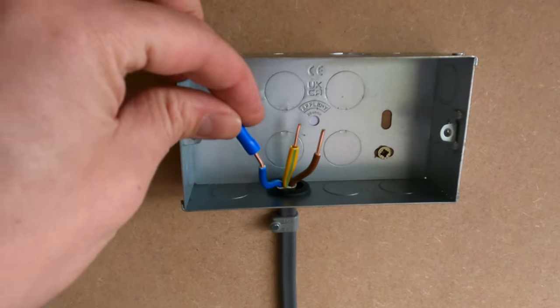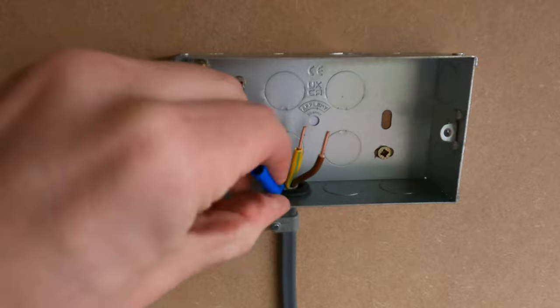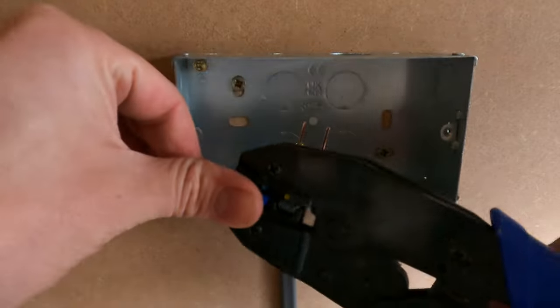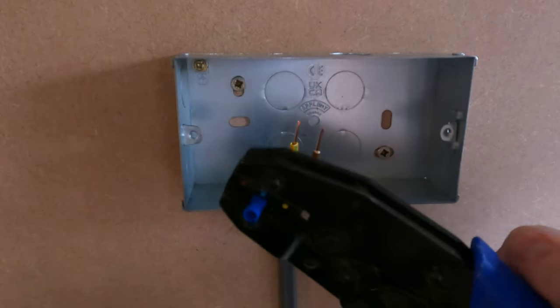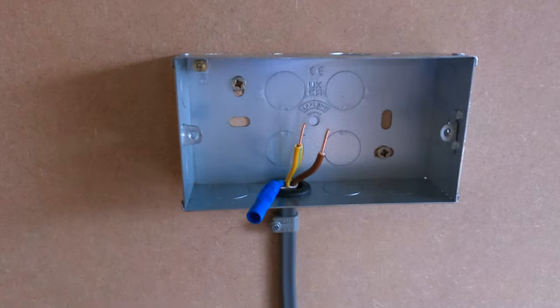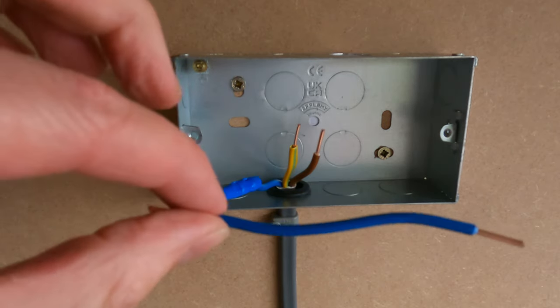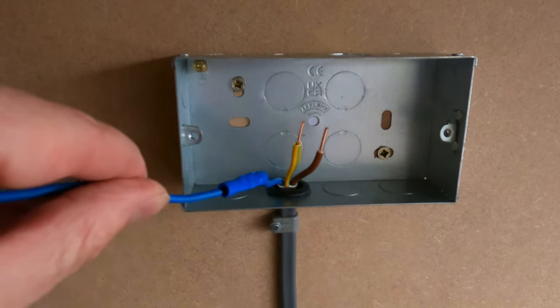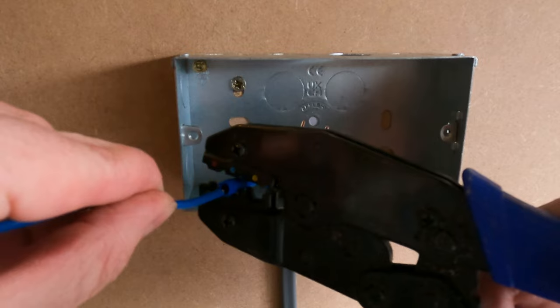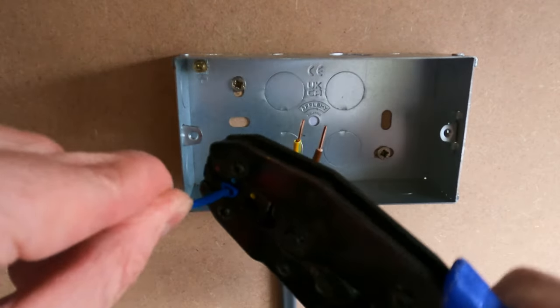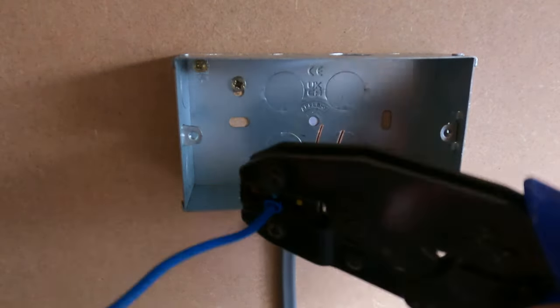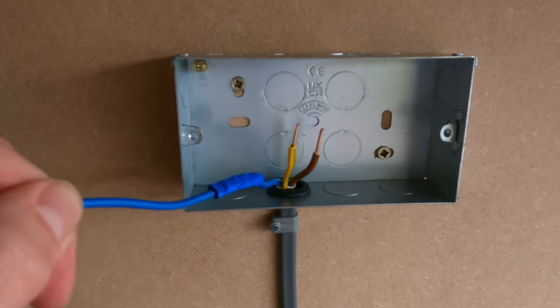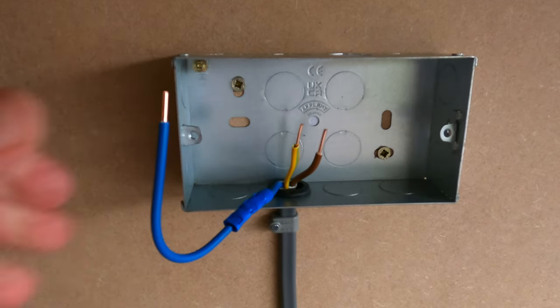So grab your crimp and pop it onto the end of the cable. Then grab your crimping tool and put it into the appropriately sized slot and squeeze down the handle. And that has crushed the crimp onto our wire. Then go ahead and grab your extended piece of wire, pop it in the crimp, line the tool up with the crimp and crush down on it. And that has ensured a good firm connection.